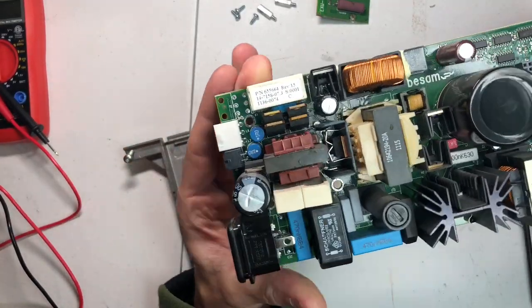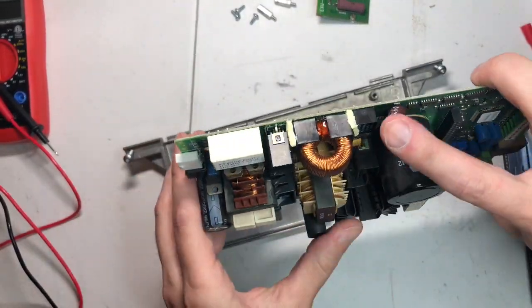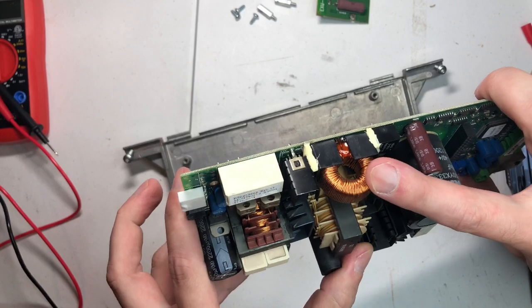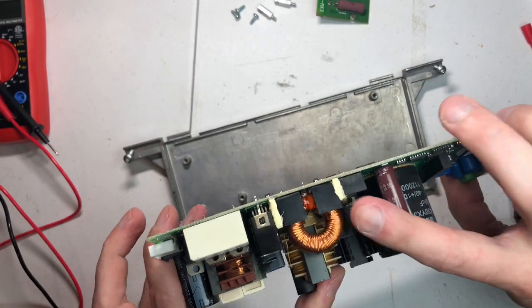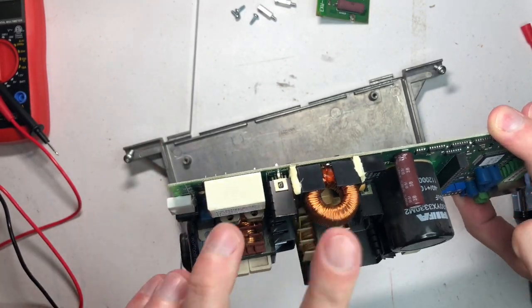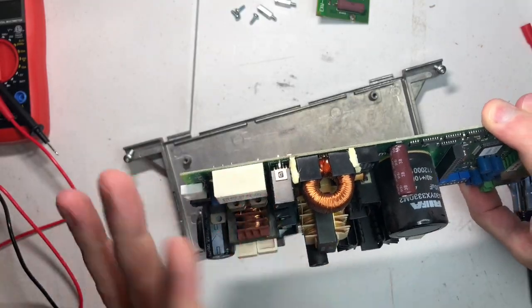So this is what it looks like on the top. You'll notice this is glued down. Vibrations in that coil. That coil will actually fall off due to the vibration.